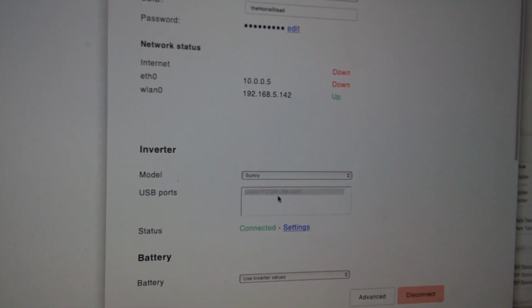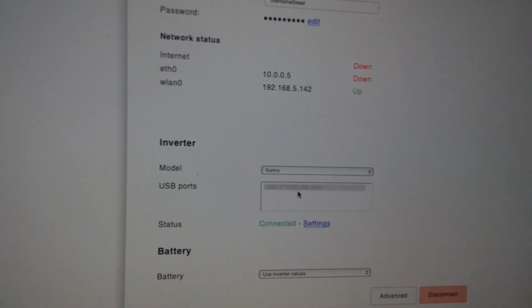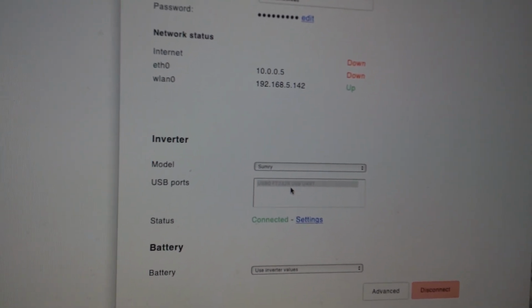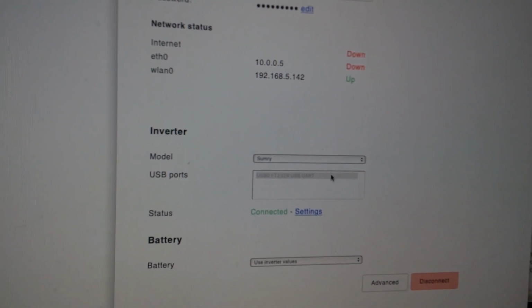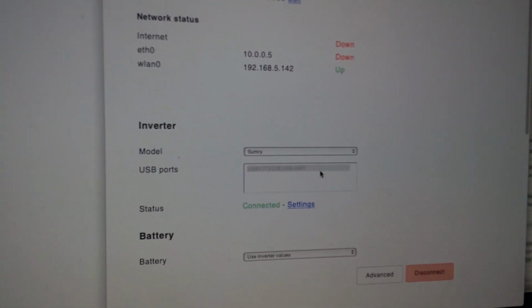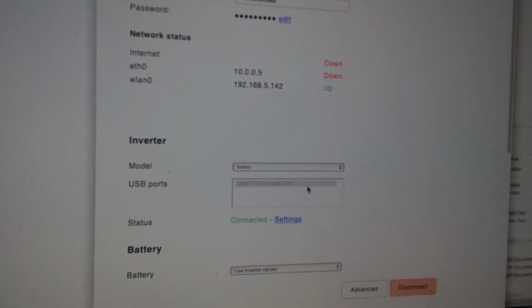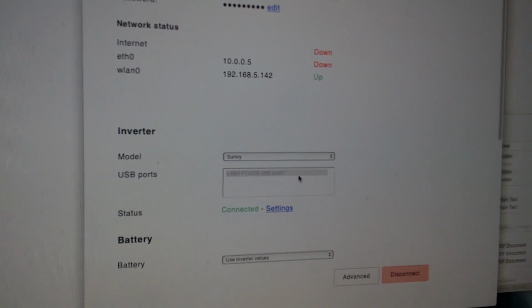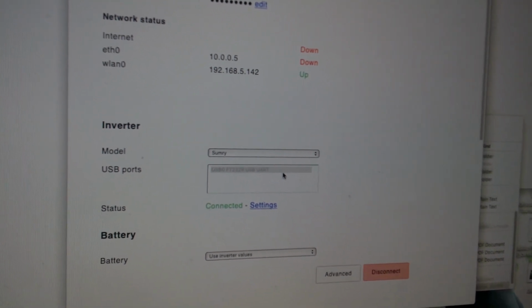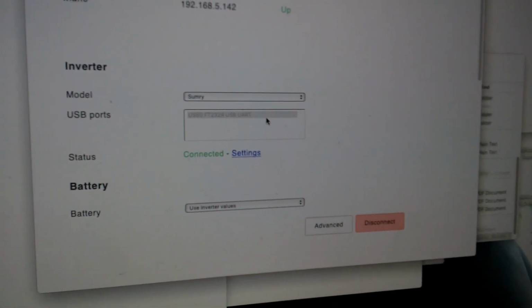And then when I unplugged that and plugged in the original unit, USB to serial, for the Solar Assistant program, then it was able to assign the address. So long story short, find another USB to serial cable, plug it in the same USB slot, pull it out, and plug in the original one, and for me it started communicating again.